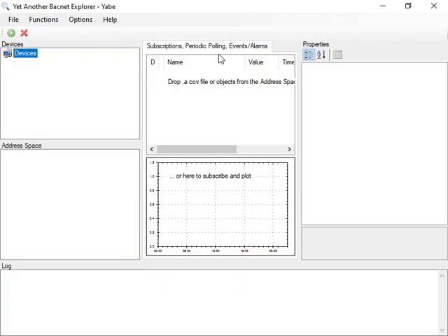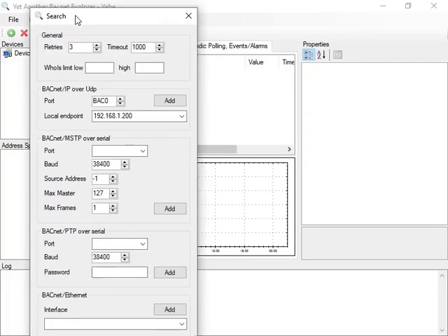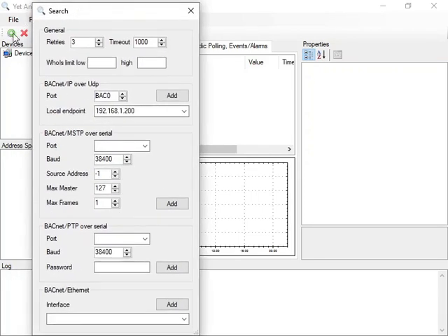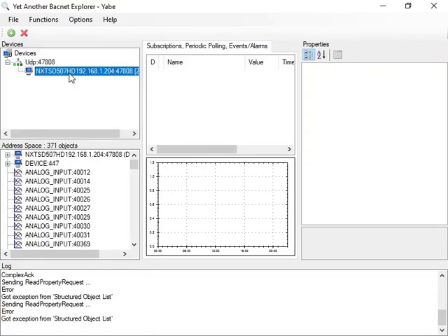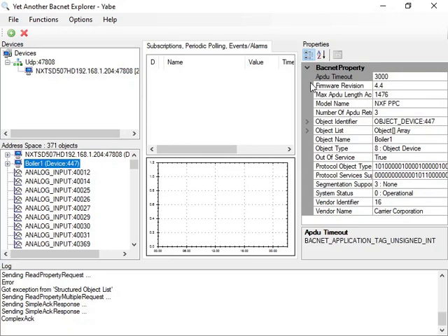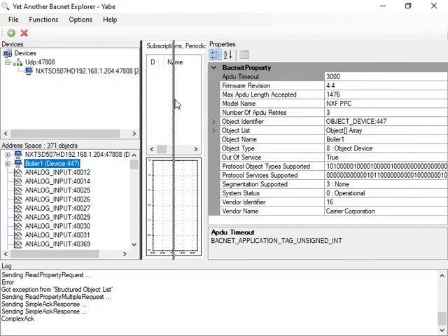Next, connect across the network with a BACnet client. In this example, we're using YABE. Select the Ethernet adapter to communicate through. After selection, NXTSD5 automatically identifies itself to the BACnet client. The connection is valid because we can see real-time data provided by NXTSD5.